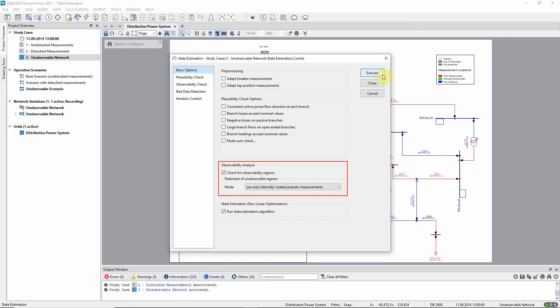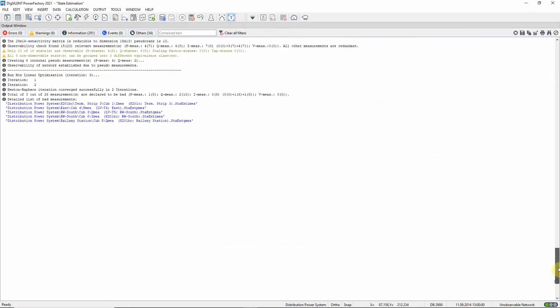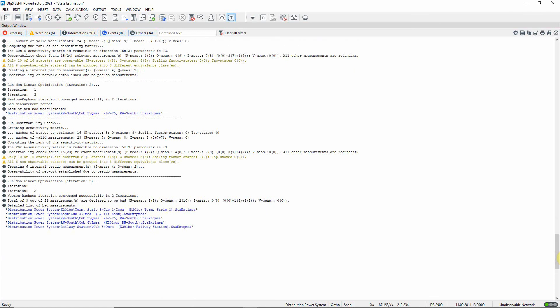We execute the command. Again, a number of bad measurements have been detected. In addition, we can see from the output that unobservable states have been detected. The user will now have to decide what actions need to be taken to improve the quality of the input data. In this case, the introduction of additional measurement locations may be required.